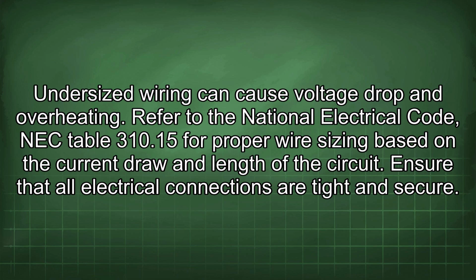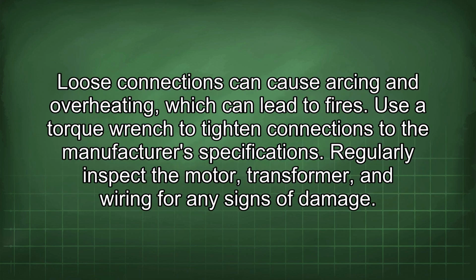Refer to the National Electrical Code, NEC Table 310.15 for proper wire sizing based on the current draw and length of the circuit. Ensure that all electrical connections are tight and secure. Loose connections can cause arcing and overheating, which can lead to fires. Use a torque wrench to tighten connections to the manufacturer's specifications.